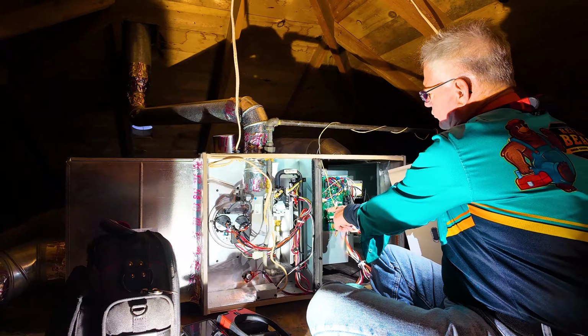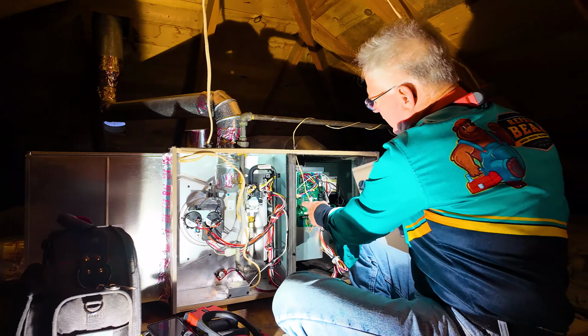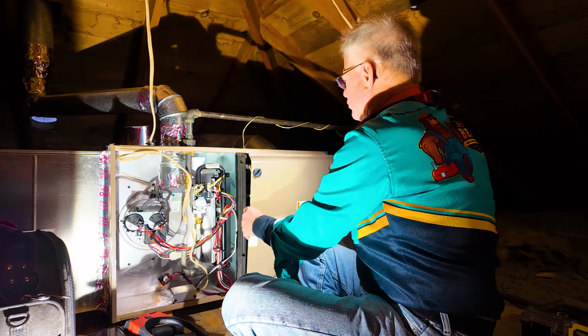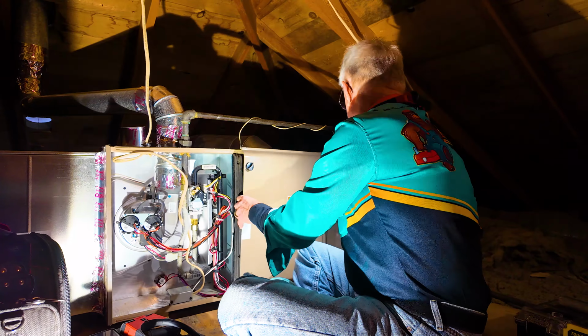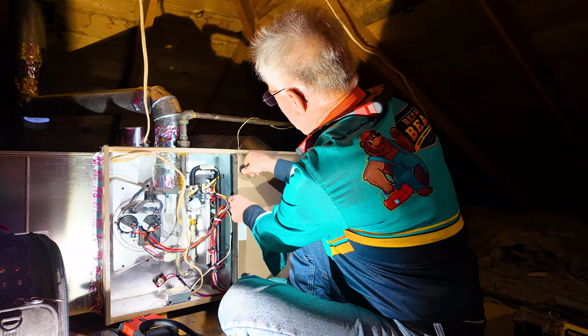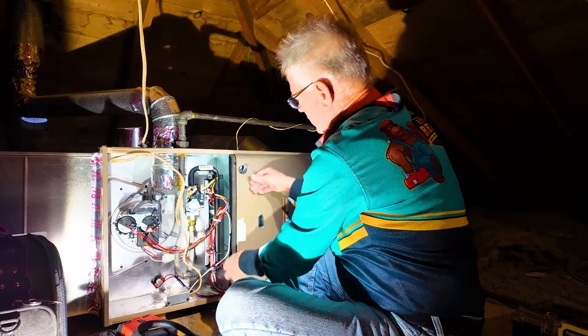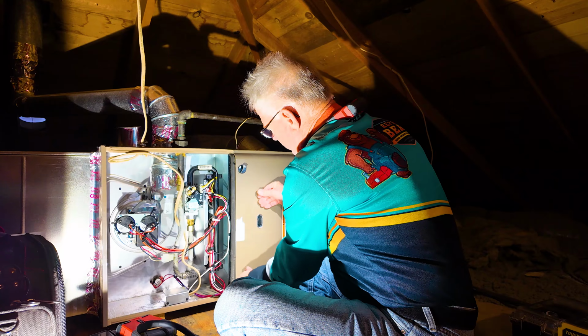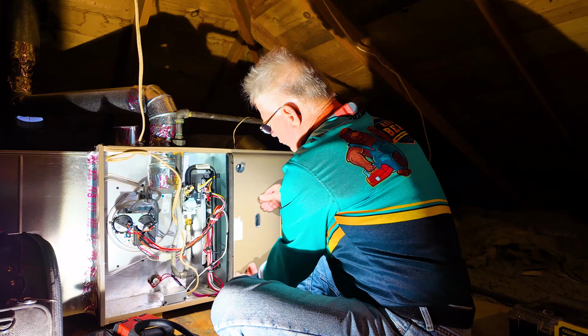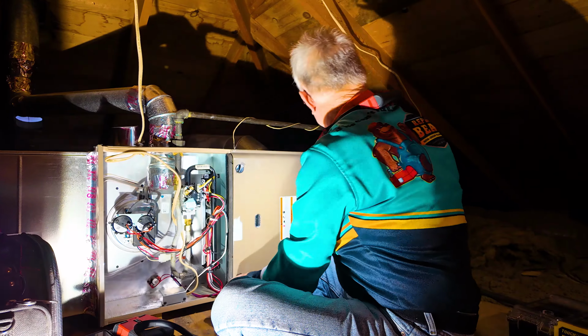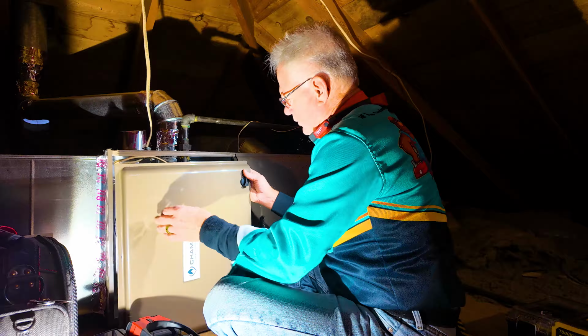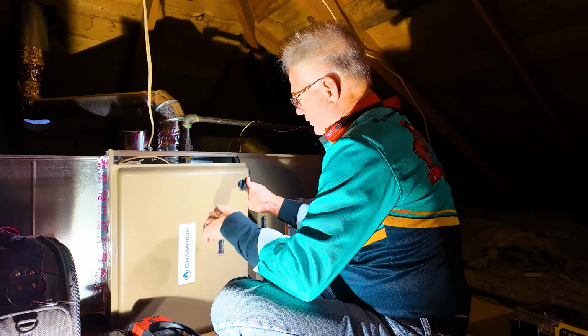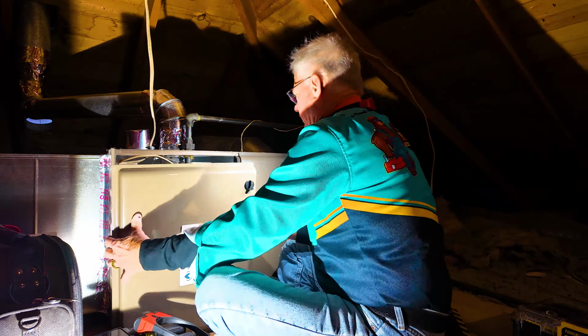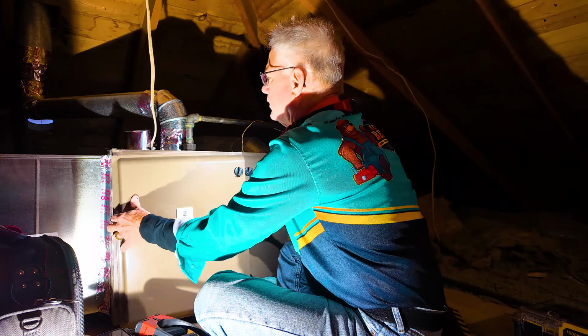And that is what is always over the board, so you can see a flash code of an LED light on that board that'll flash codes if it has some kind of a code or error condition. And that's important, because on the inside of the same door, you'll have writing on there with labels like this one I just put on, and it'll have the flash code diagnostics. I see this one has it on both, so I guess you could interchange these doors. It wouldn't make any difference on this brand.